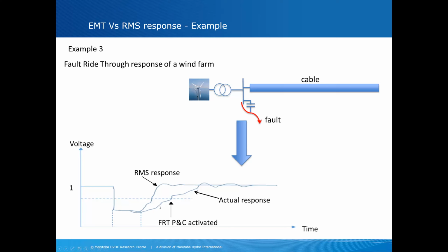But if you look at the real measurements, this is a measurement that came from the field, the one on the bottom. Up until the point where the fault got cleared, there was a slow recovery. Before the system reached its tolerance threshold, the controls and protection got activated, and then there was a signal to trip the wind farm. However, the same modeling in RMS was signaling that the wind farm has recovered and the fault ride-through has passed. So in one condition, in RMS, fault ride-through passes; in reality, there was a tripping of the wind farm.